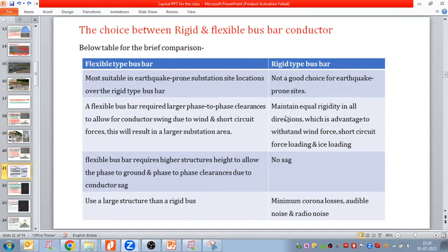So, if you have less space and this is not an earthquake prone site, we can think of the rigid type bus bar. Flexible bus bar requires higher structure height to allow the phase to ground and phase to phase clearances due to the conductor sag. In the rigid, there is no sag. It uses a larger structure than rigid bus bar. In the tube we have the minimum corona loss, minimum audible noise, and minimum radio noise.